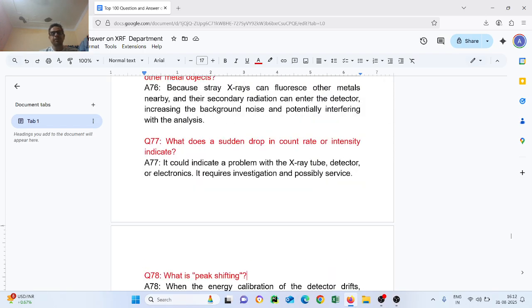Question number 77. What does a sudden drop in count rate or intensity indicate? It could indicate a problem with the X-ray tube, detector, or electronics. It requires investigation and possibly service.